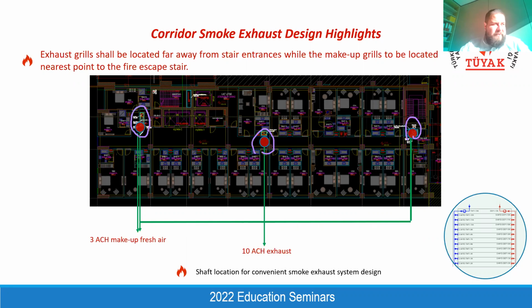And the shaft locations are approved by the architect. Even if the mechanical designers send you wrong shaft locations, you need to inform them that the exhaust shafts shall be as far as possible from the fire escape stairs, and the makeup shafts, makeup grills should be located just next to the staircase. This is your responsibility. You need to check the design. You need to coordinate the mechanical shaft locations that come from the mechanical designer. That's why it's really helpful for you to execute a good design, a convenient and suitable design from the smoke exhaust point of view.